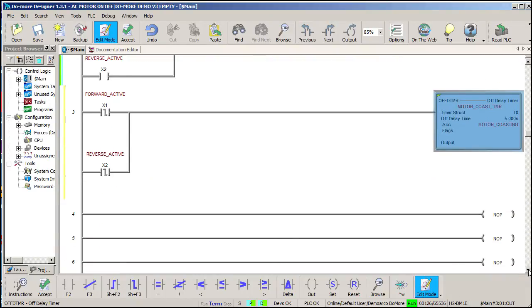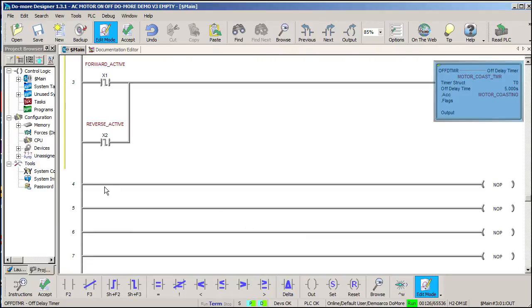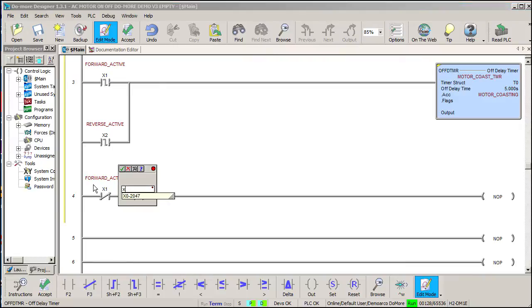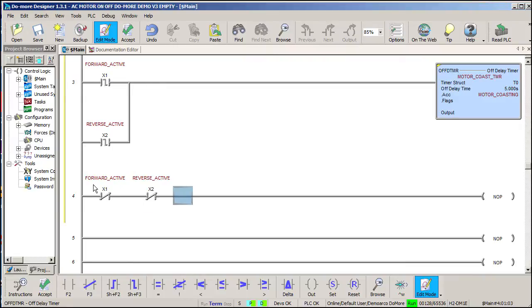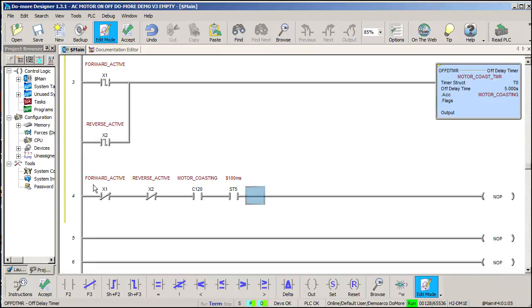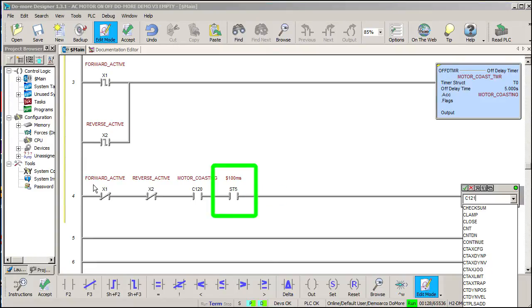Now we can use that motor coasting bit to create the flashing stop indicator. If the reverse and the forward contactor are not active, but the motor IS coasting, we'll set a bit to indicate that the motor is still active. If we add the system 100 millisecond bit here, it will make the light flash.